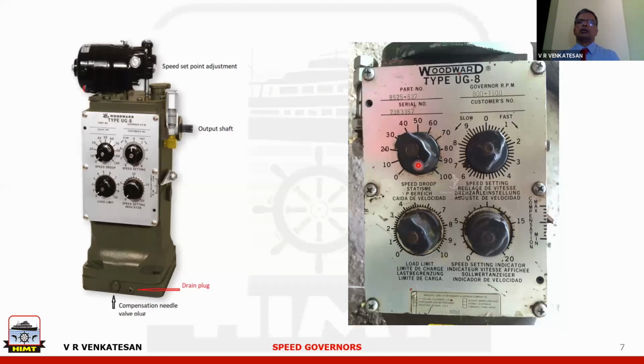This is the speed setting, speed droop setting. It is showing in percentage, 0 to 100 like this. So currently it is something like 30%. So 30% droop setting means it is 30% of the maximum possible droop setting. So the maximum possible droop setting could be 4%.